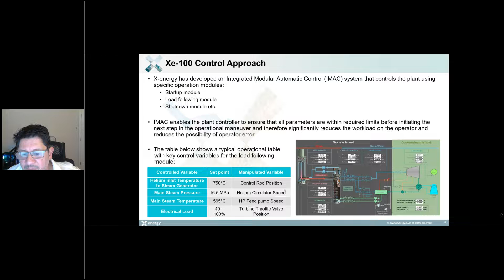If you close the valve, the pressure increases, and our control system will automatically recognize that and reduce the power on the reactor side. So it's a very simplistic control system, no complex control loops, and that's also a big improvement when it comes to regulatory review of the distributed control system. It has been so much simplified that there's no safety related component in our DCS, our distributed control system. The only safety related control part is our reactor protection system, which really just trips various aspects of the plant. So that's helped us also reduce costs significantly on the nuclear island.